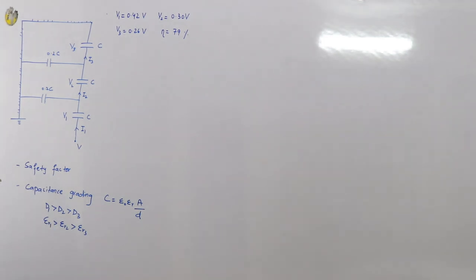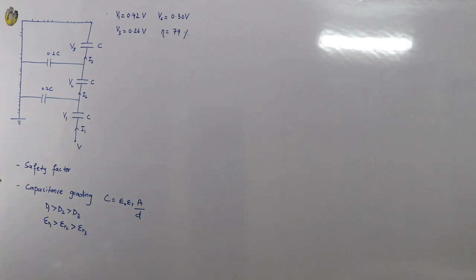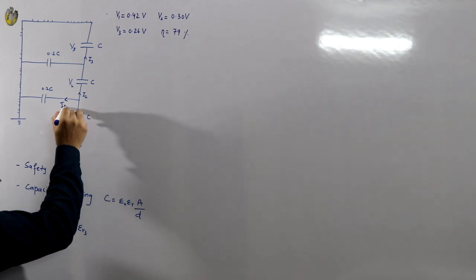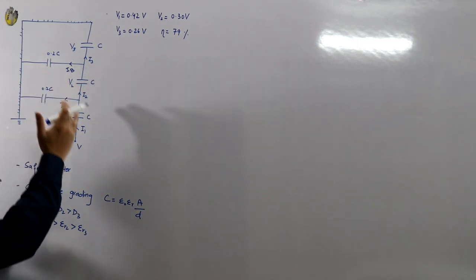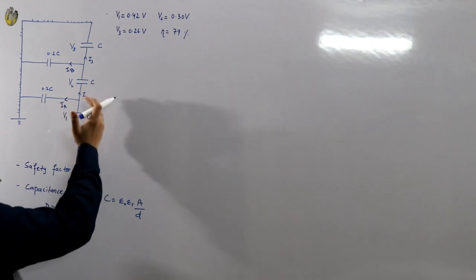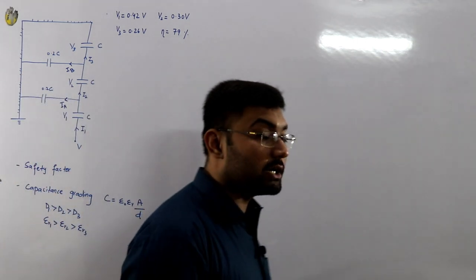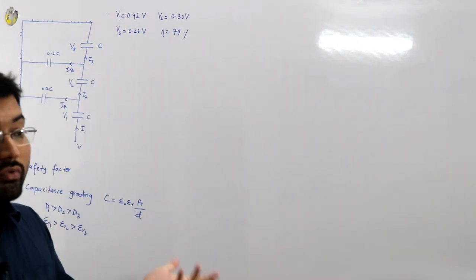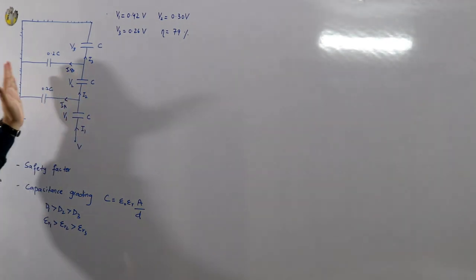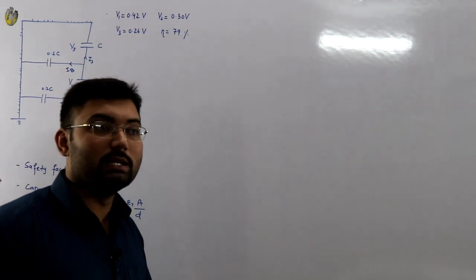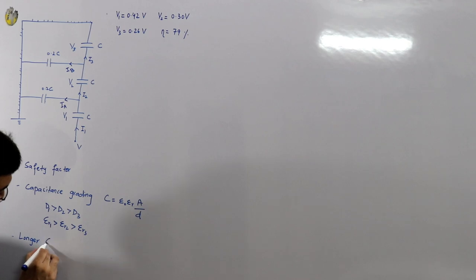Coming back to basics: what is causing the problem? The problem is caused by the leakage currents Iₐ and I_b from the shunt capacitances. If these shunt capacitances were not present, I₁ = I₂ = I₃ and voltages would be equal in this series circuit. To negate the shunt capacitance effect, one idea is to move the string farther from the grounding structure by using a longer cross arm.